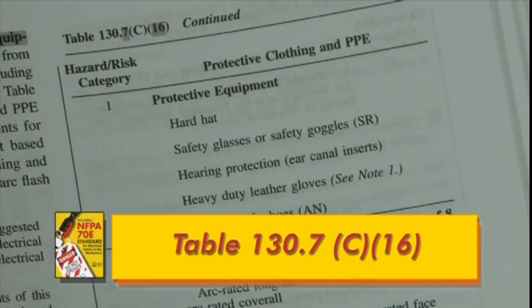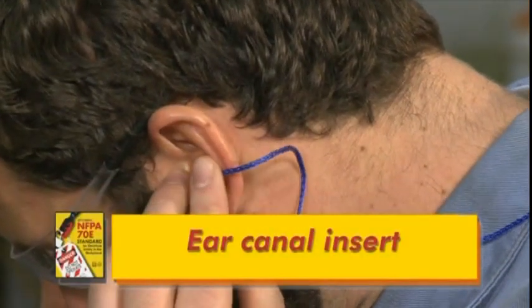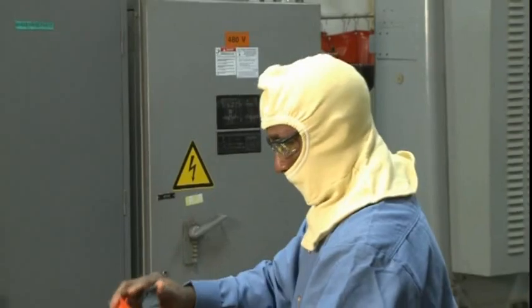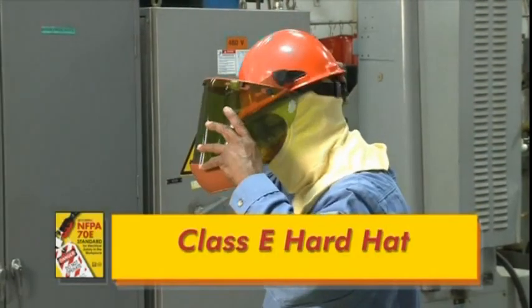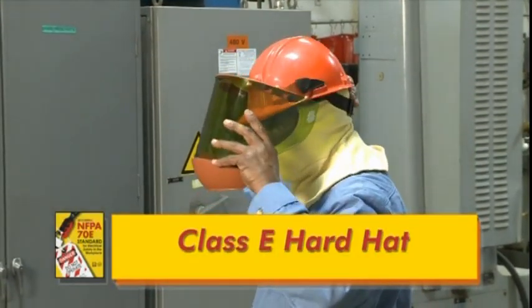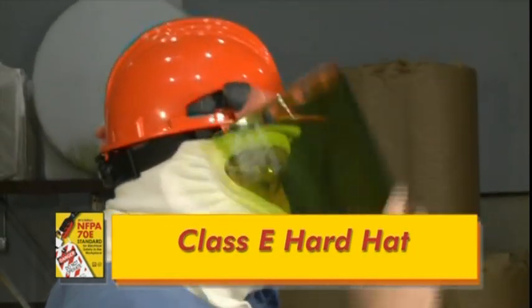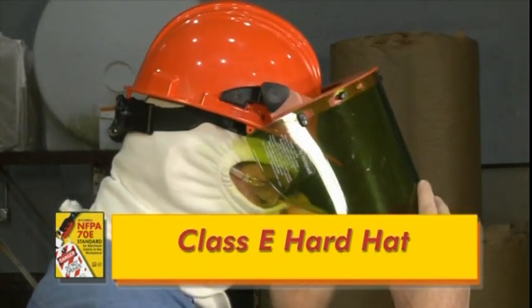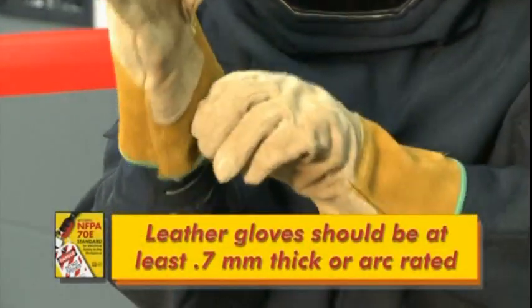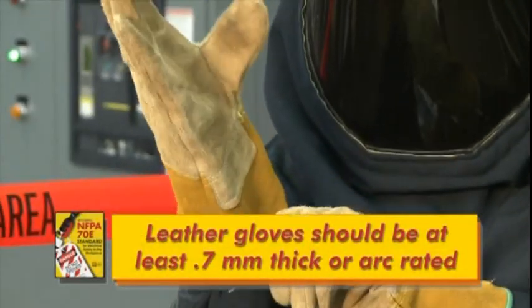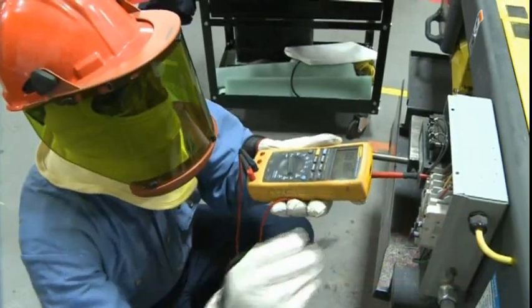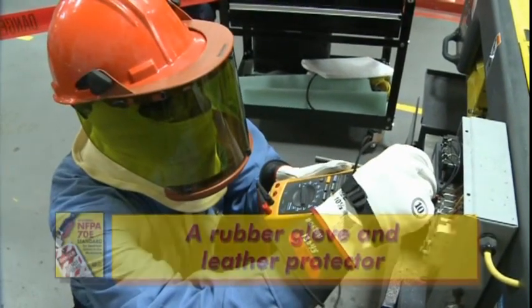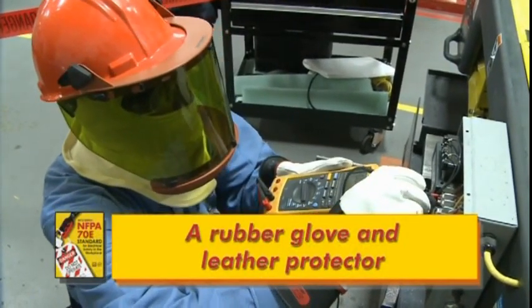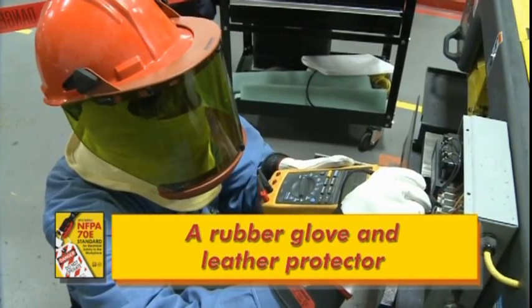Some common PPE elements in this table are hearing protection, leather gloves, and a hard hat. When hearing protection is required, it should be an ear canal insert. When a hard hat is required, it is to be a dielectric hard hat. Typically a Class E hard hat rated for electrical work up to 20,000 volts is used. And when leather gloves are required, they shall be at least 0.7 millimeters thick or arc rated. If rubber insulating gloves are to be worn, the combination of rubber glove and leather protector meets the requirements for a leather glove.